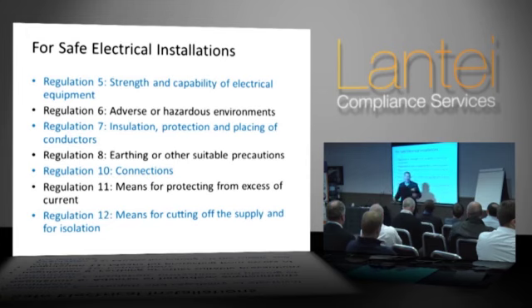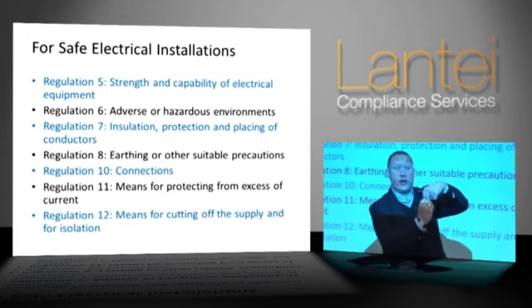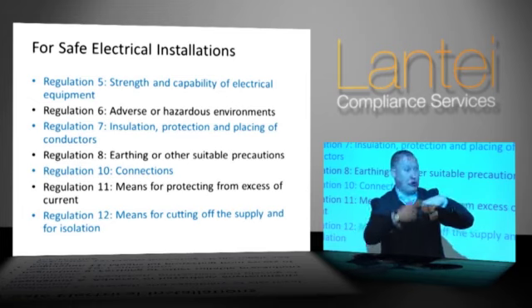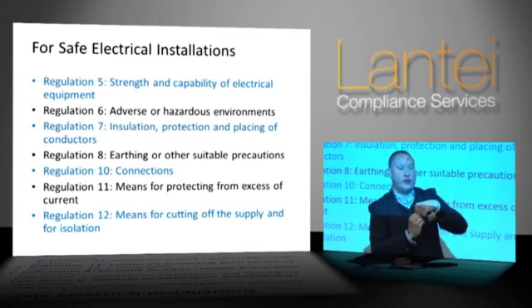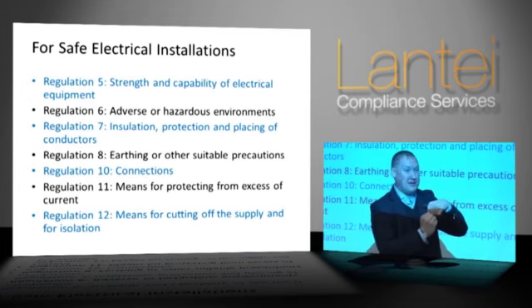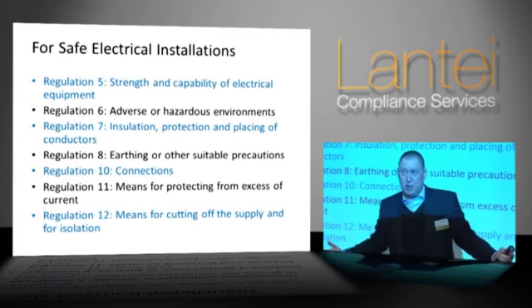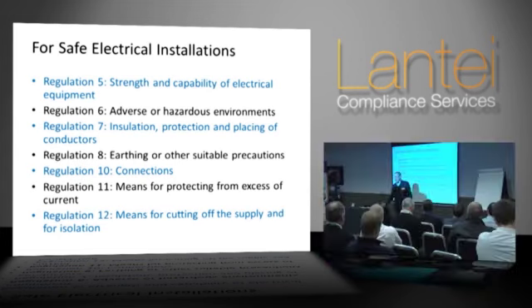If you think about it, in our isolator we've got two metal contacts touching each other. They're getting hot due to the electrical current going through them. What condition's going to occur there? It's going to weld, isn't it? What's the last thing you want an isolator to do? Weld together so you can't turn the damn thing off. Exactly, and that's where Reg 5's coming from.